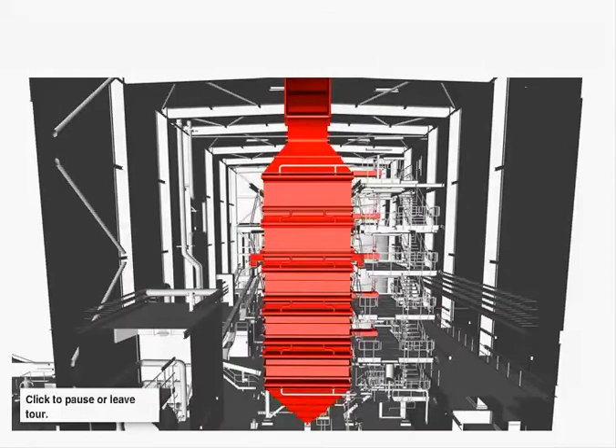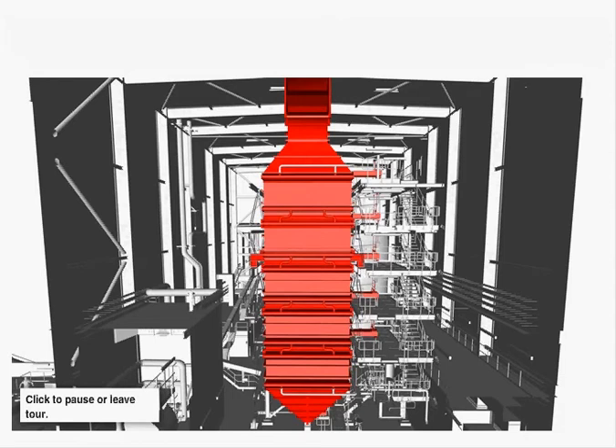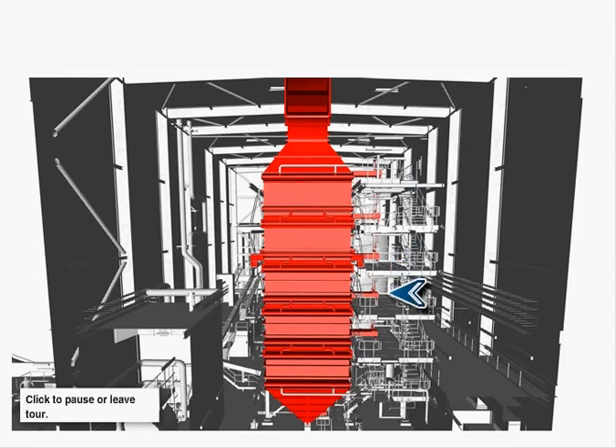The economizer consists of thousands of water tubes that cool down the flue gas and thereby recover as much energy as possible. We're using steam soot blowers for online cleaning of the economizer. We're able to precisely control the boiler flue gas outlet temperature to within just a few degrees Celsius. This results in very high efficiency.